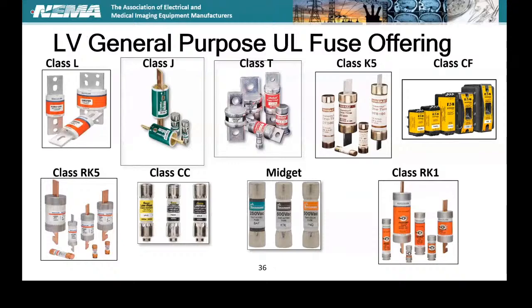So here we go. Here are our general purpose fuse offerings. We've got Class L. I'm going to go through a list of all of these, and we've got characteristics for all of them. So here are our Class CC fuses. Now remember those questions I asked earlier? Here we are: 30 amperes or less for a Class CC fuse. Current limiting, optional time delay, with an interrupting rating of 200,000 amps. All sizes are 10 by 38 millimeters with a rejection feature, and UL listed for branch circuit protection.